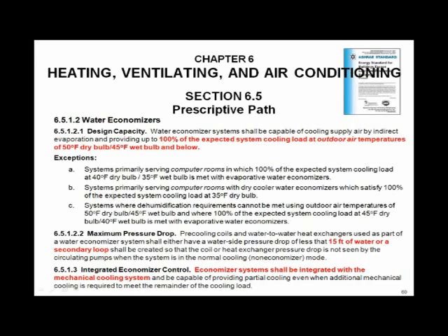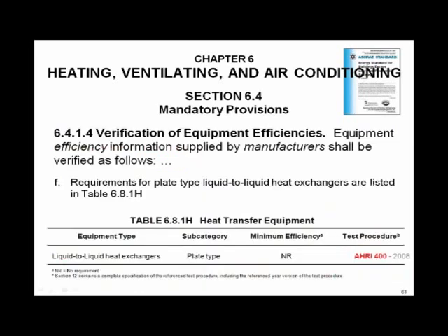Translation. You want to be able to run the waterside economizer, you want to be able to run your chillers at the same time you're running your waterside economizer. You want them in series. You want them integrated. It's not either or. It's not on-off. You want to integrate the two so they gradually swing over. That is a huge change. And you need to be thinking about how you're going to deal with it piping-wise on cooling towers. We'll get deeper.